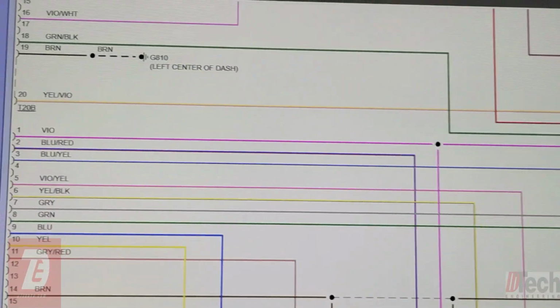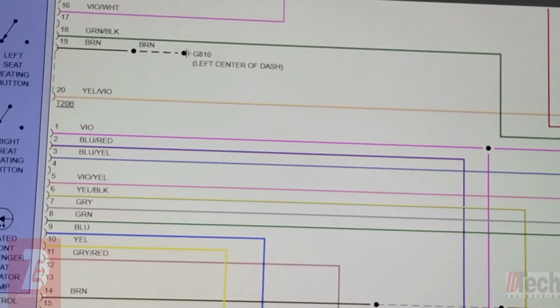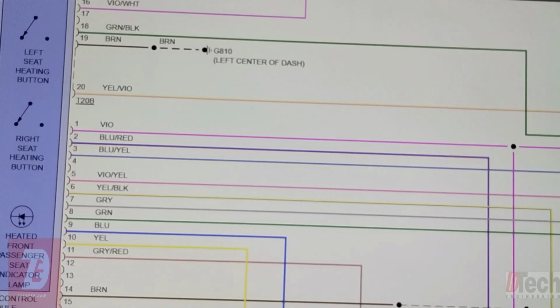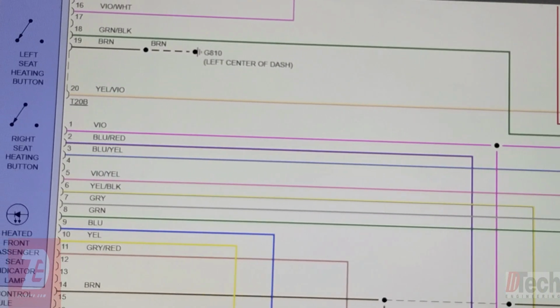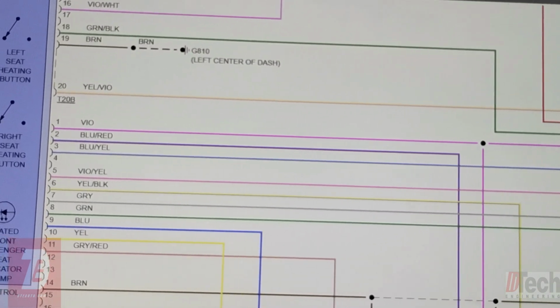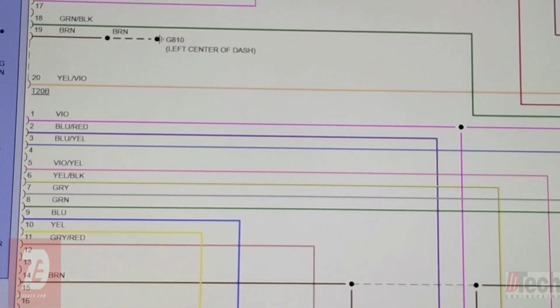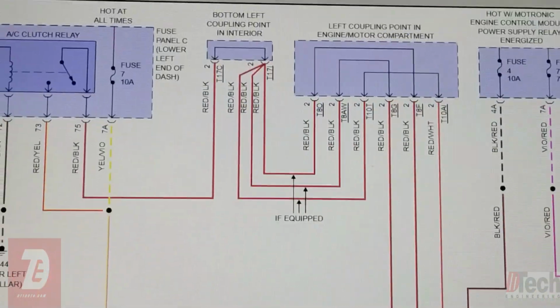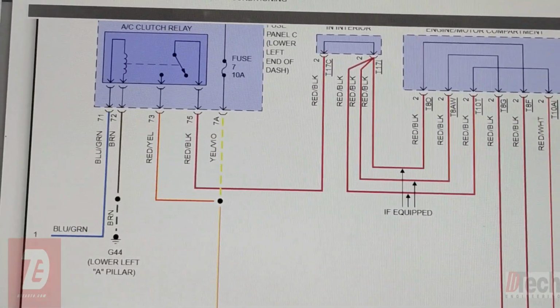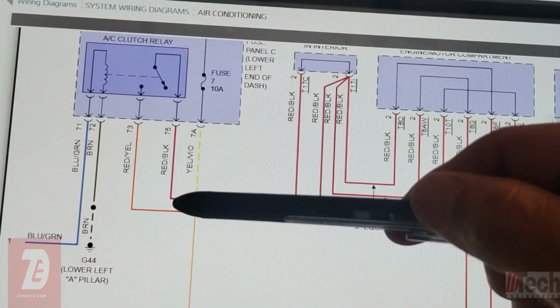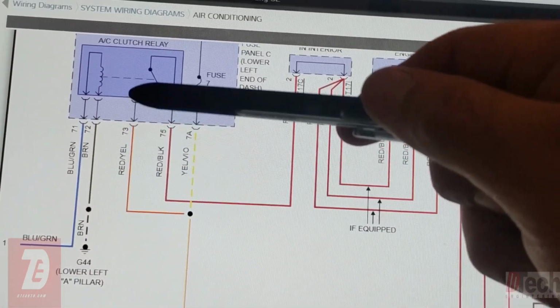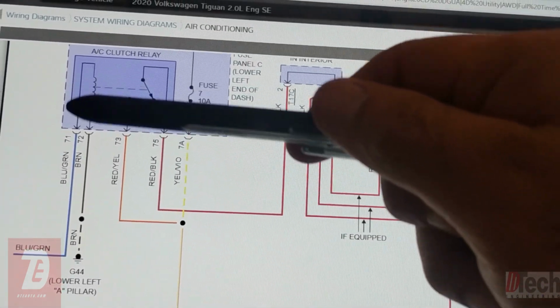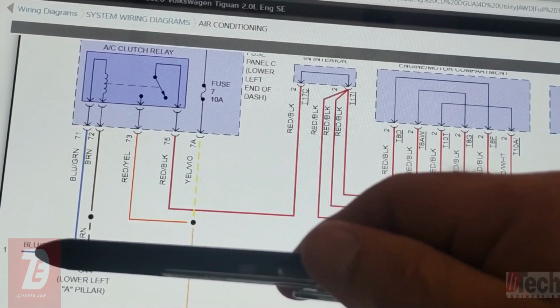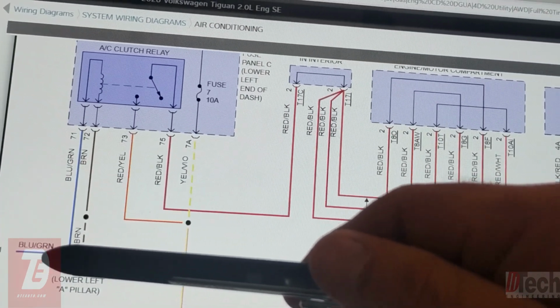That's where we had our amp clamp. We know that line, that feed on that pin to that module, is not the one carrying the high amperage. We're looking for amperage above 10 amps. So let's go back to this split point. It splits and feeds here on what they call the AC clutch relay, and it'll activate through the HVAC control module.